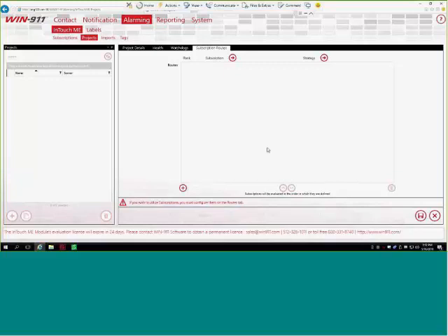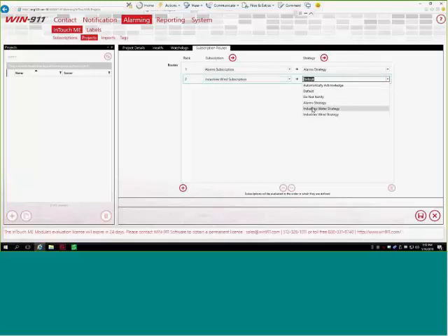And then the last thing, our subscription routes. We created those subscriptions already, but now we need to apply them to the project. So if I click this plus button, here are all the subscriptions I made, and here are the strategies that I made. If I hit the drop down, I'm going to create this alarm subscription. That's going to give me the SIM alarms from Web Studio, and I'm going to send that to the alarm strategy that I made. I'm not going to bring in the water alarms because they go in and out of alarm constantly, and I don't want to send hundreds of emails right now, so we'll just ignore that one for now, and we'll do wind alarms too.